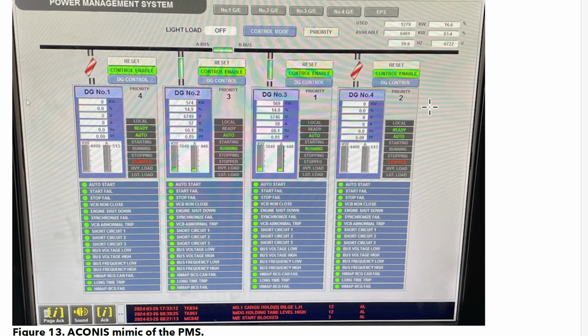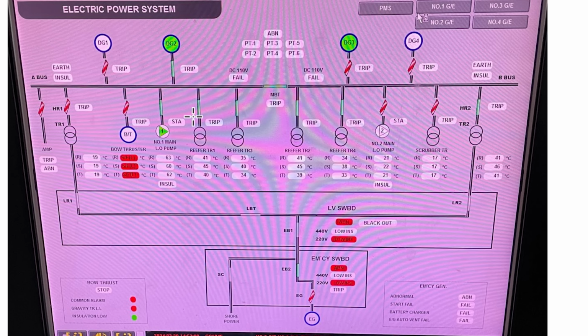The power management system looks like this in the control room. When everything's up and running perfectly, this is what it should look like, and when you have issues, this is what it would look like. Here you can see diesel generator 1 is tripped, HR1 is tripped, and diesel generator 3 and 4 are also tripped. This lets you know when a circuit breaker has tripped.